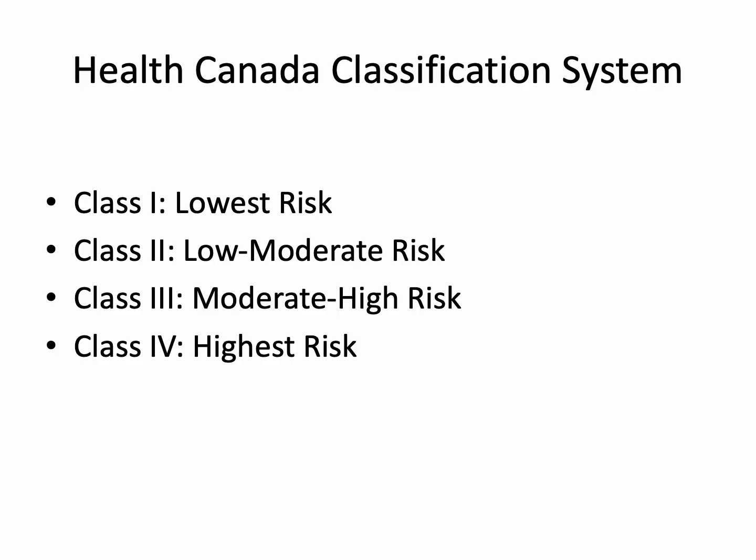Class 3 devices, including orthopedic implants and glucose monitors, are moderate-high risk, necessitating an MDEL plus an MDL with supporting safety and effectiveness data. Class 4 devices, such as pacemakers and HIV test kits, are highest risk, requiring an MDEL and an MDL with extensive clinical evidence.